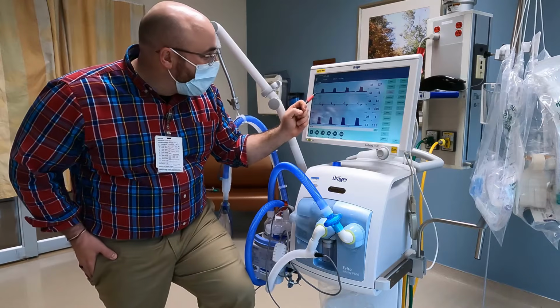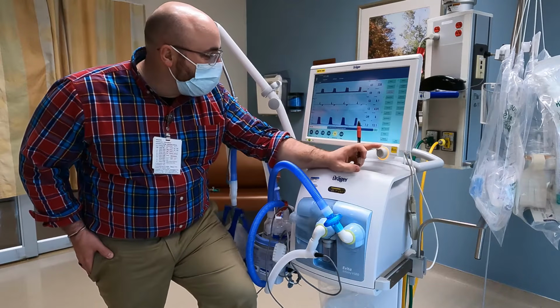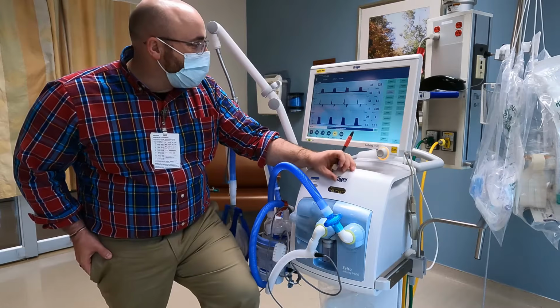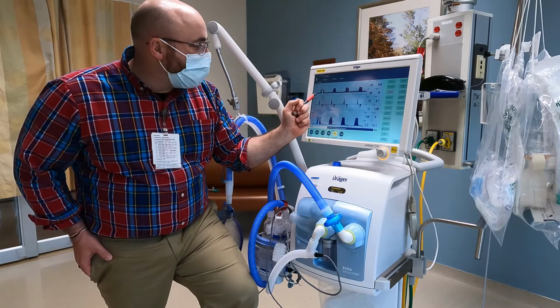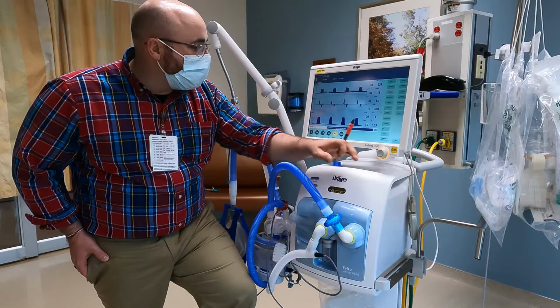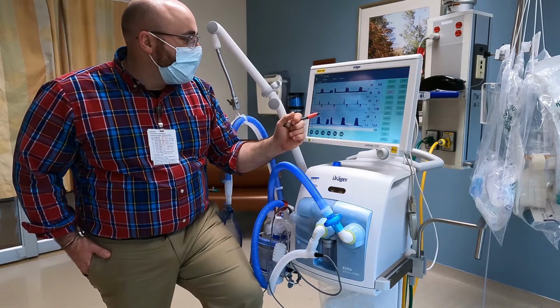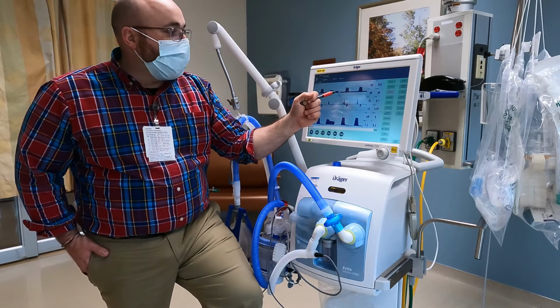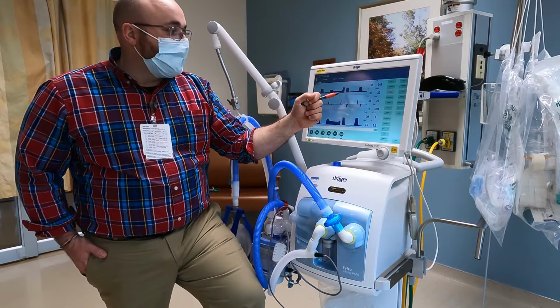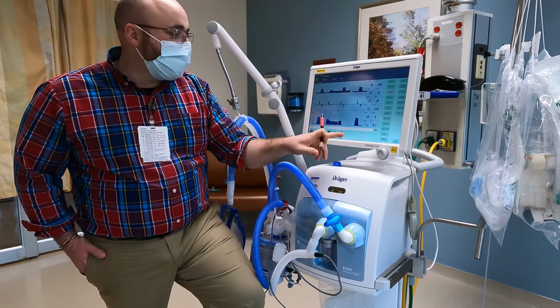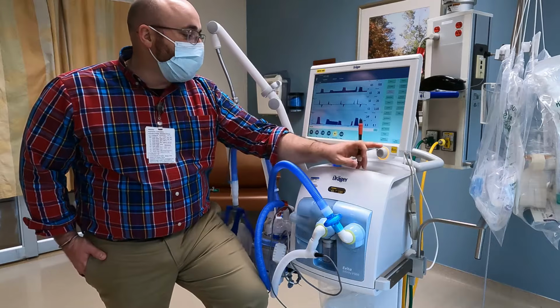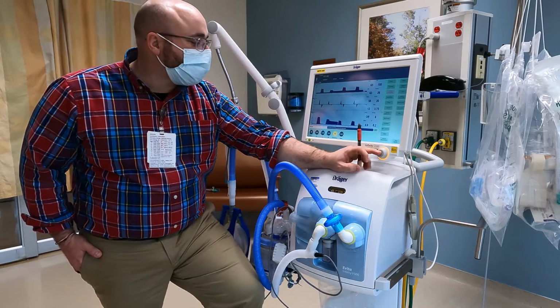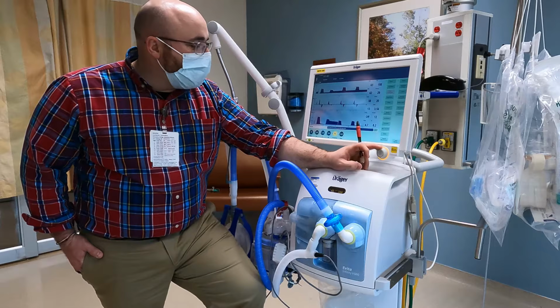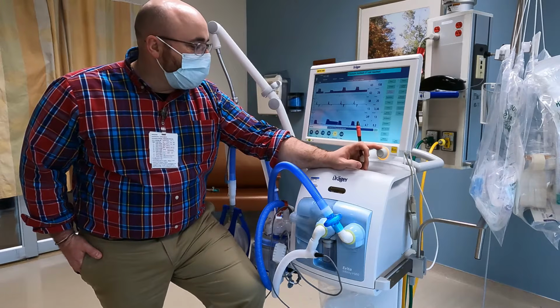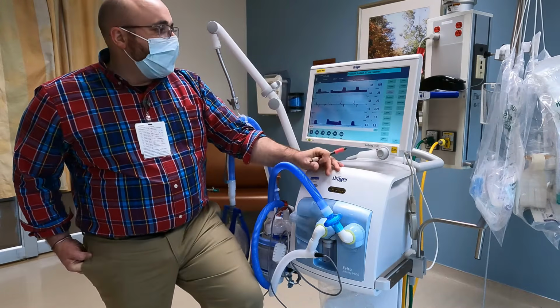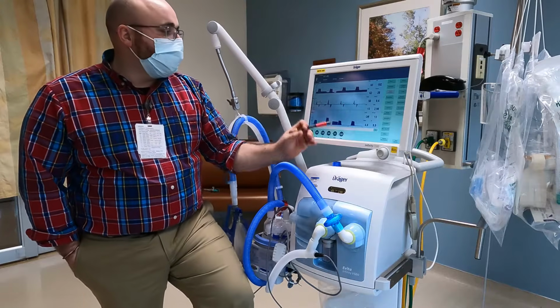So see that little line right there? That's at 8. If I turn it up, watch what happens to the line after the next breath. Look at that. That's your PEEP now. Well, it's really high. So you see it doesn't come back down to baseline because I turned that PEEP up. So that is your PEEP. That's your pressure waveform on the top. We try to keep 8 of PEEP, and that's just to prevent ventilator-associated events. Pressure limited breath again, so you see what happens there.